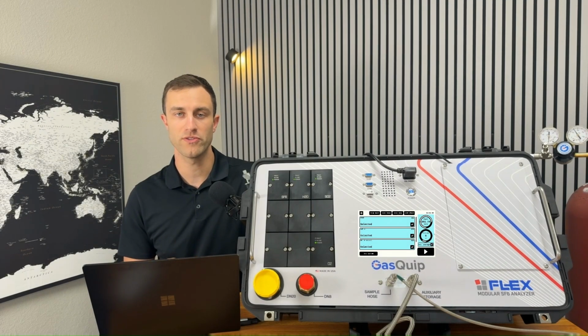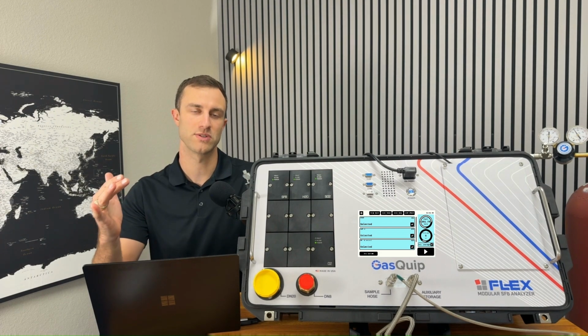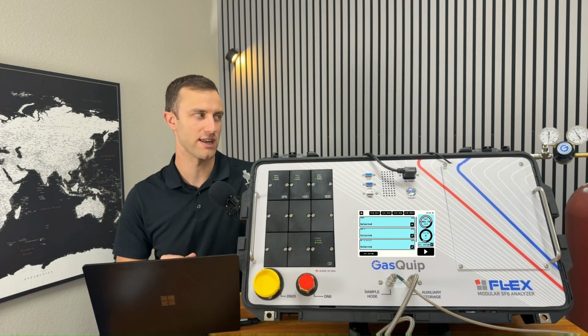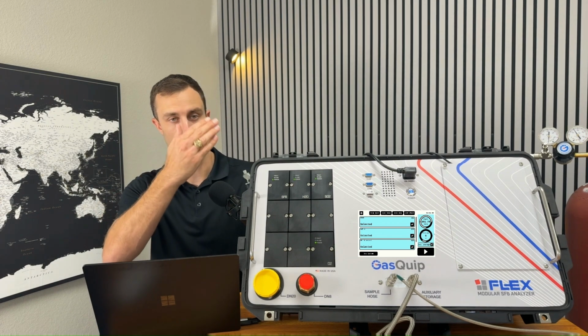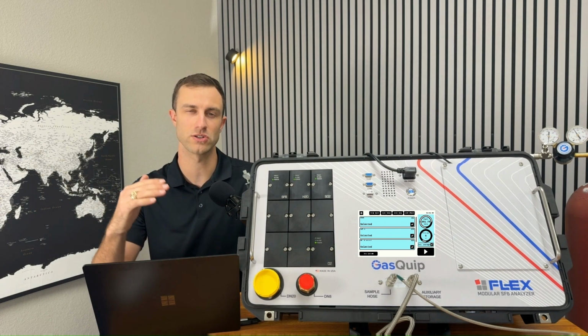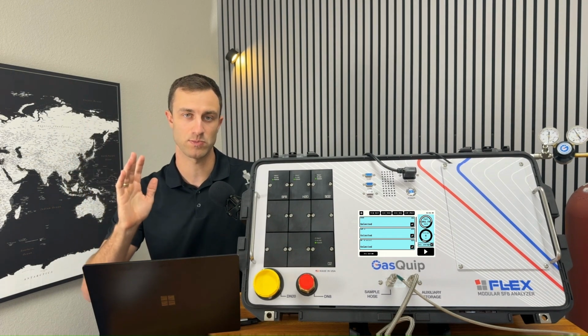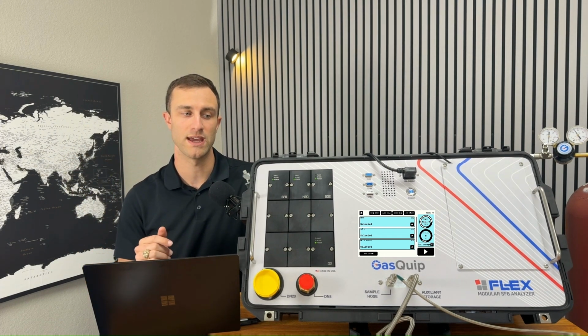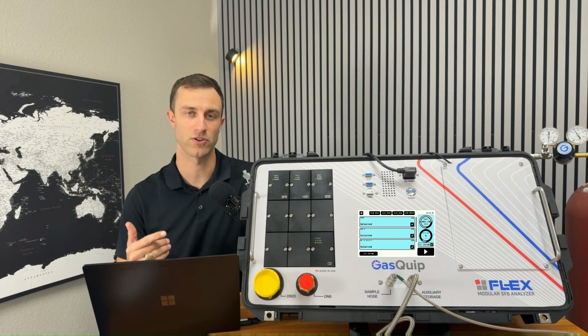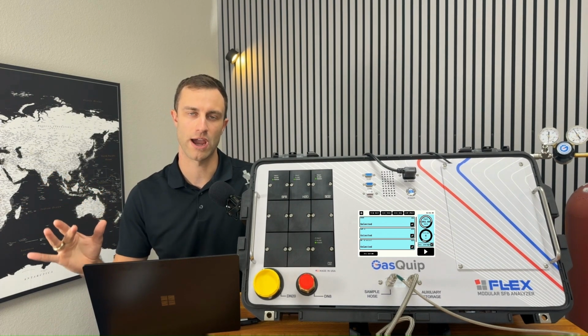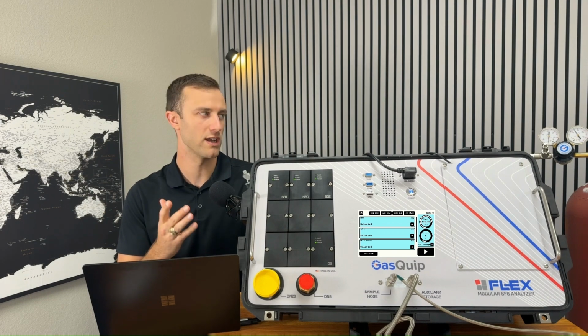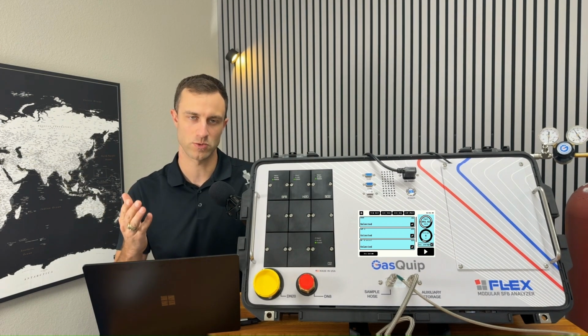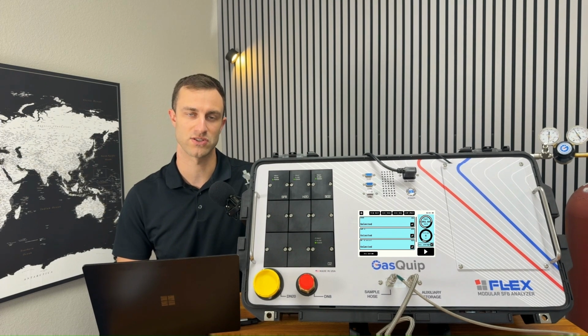Also, it is very normal, if you're testing a bottle of gas, to have the first test a little bit wetter than you're expecting, and then subsequent tests dry out. The reason is that the dry gas running through the hose, the fittings, the regulator, and the analyzer is drying out that gas path along with the tip of the sensor. If you run a few more tests on top of the first test, it tends to show a drier and drier result. We'll get into some of the more troubleshooting things later, but that's what you should expect to see if you are testing on a bottle or a dry breaker as well.